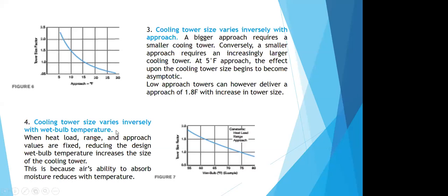Fourth important concept in cooling tower sizing is that the cooling tower size varies inversely with the wet bulb temperature. So keeping the heat load, the range, and the approach constant, if you reduce your wet bulb temperature, say if it is Delhi, we talk about say 83 degree Fahrenheit, and we select a tower here. And if we take the same tower to a place up north, maybe Himachal or Jammu, where the wet bulb is lower than Delhi, the tower will not be able to perform as per the required design temperature or duty condition, because the air's ability to absorb moisture reduces as the temperature reduces. So these are 4 key concepts that one needs to keep in mind about tower sizing and its importance in low approach cooling towers.